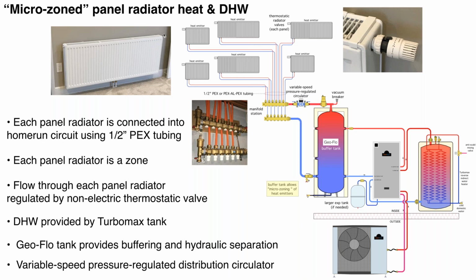And the other thing I want to point out, you'll see this knob here in this upper right corner. Here's kind of a zoomed in picture of it. This is the thermostat for the room. There's no wires, there's no batteries. And basically you just turn that knob. You see right now it's set for the number 3. And there are no temperatures indicated on these knobs. And that's kind of a smart move from several standpoints, one of which is you can sell it to people that use Fahrenheit as well as people that use Celsius. There's numbers from 1 to 5, and a typical indoor comfort setting, approximately 68 to 70 degrees Fahrenheit, would correspond to a number 3 here. So you see it's set at 3.